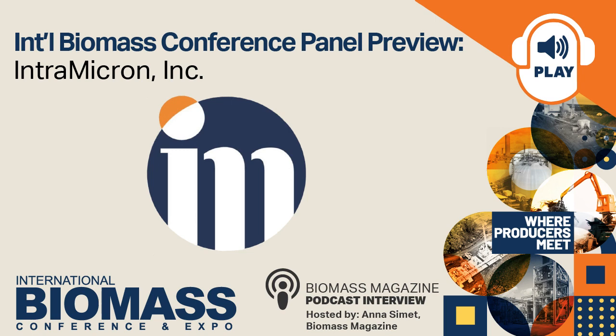And it kind of provides this middle ground between the simplicity you get by a simple scavenger system, but the benefits you would get from a more complex multi-step catalytic system that's commonly used most of the time in the petrochemical industry. More often in the RNG space, biological systems are used. However, from a lot of the people that we've talked to, they can be awfully temperamental. And if you don't keep the bacteria happy and the solution chemistry happy, it can be a challenge. Whereas with ours, we're doing all the chemistry in the gas phase to convert that hydrogen sulfide and recover it as elemental sulfur. So it does provide a level of simplicity from that front.